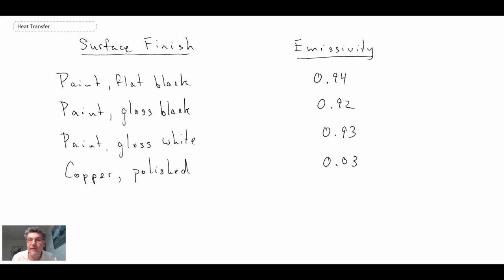So there we have the emissivities for the different surfaces. And you can see for all of the painted surfaces that we looked at, the emissivities are all pretty close. 0.93, 0.92, 0.94.